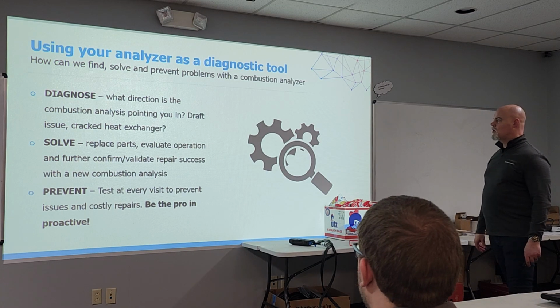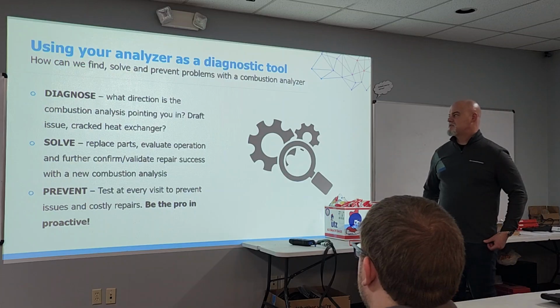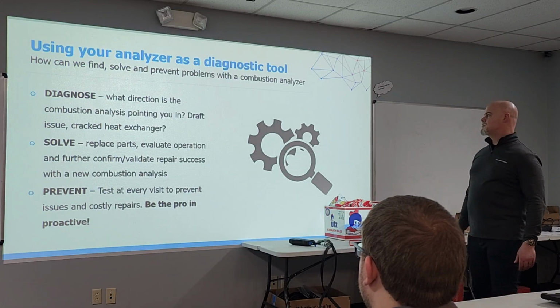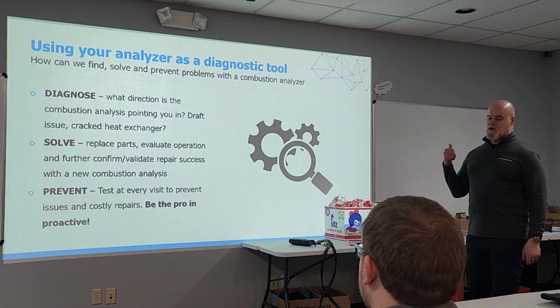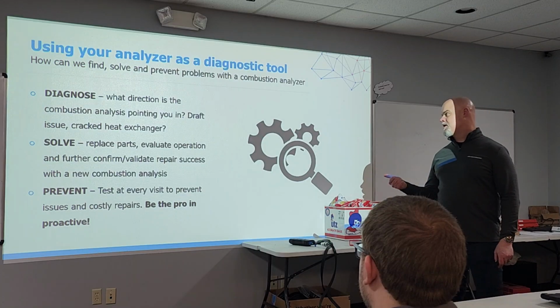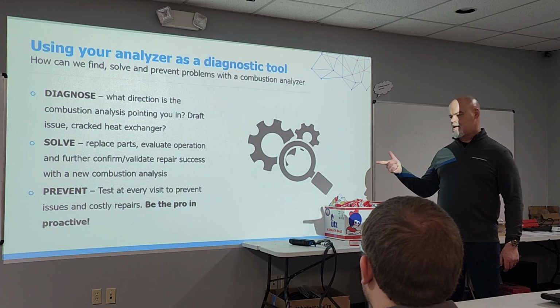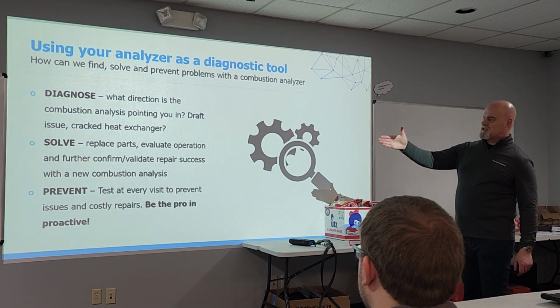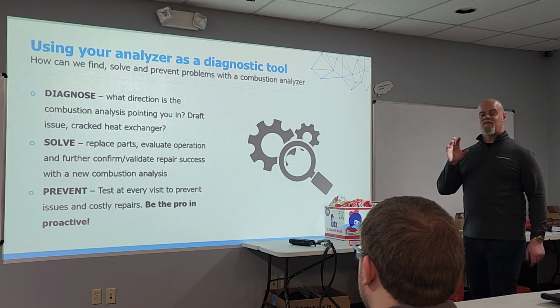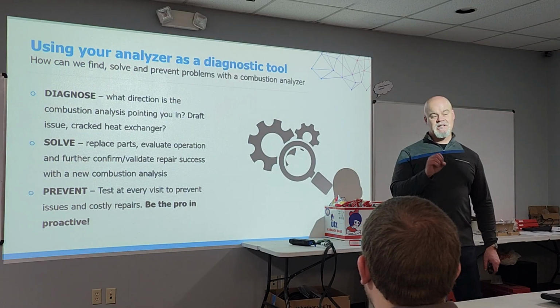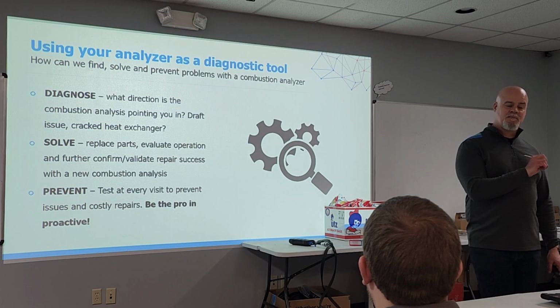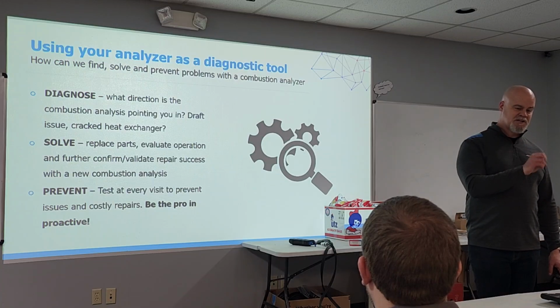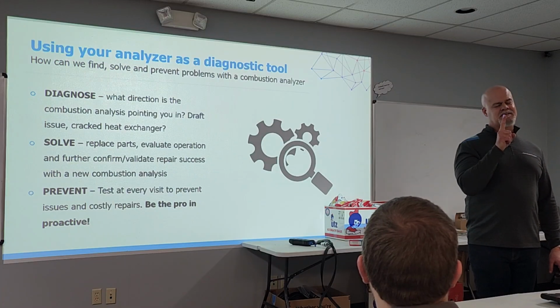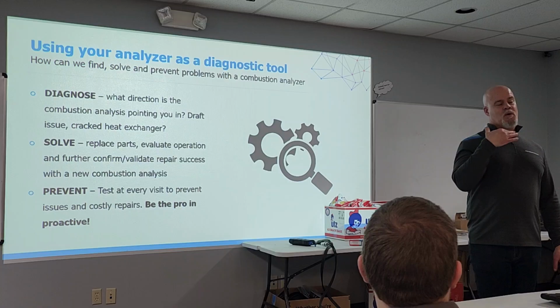Diagnostics, here we go. Using your analyzer as a diagnostic tool. How can we find, solve, and prevent problems with a combustion analyzer? Diagnose. What direction is the combustion analysis pointing you in? Do we have a draft issue? Do we have a cracked heat exchanger issue? Then you're gonna solve. When you verify through the readings what parts need to be replaced or what adjustments need to be made, you're going to make said adjustments or replace said parts, and you're going to test again.